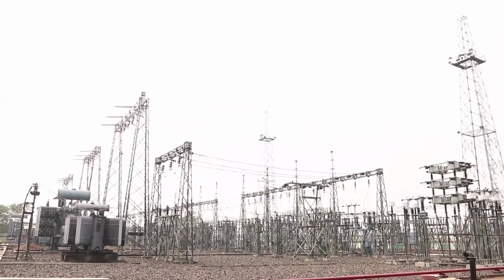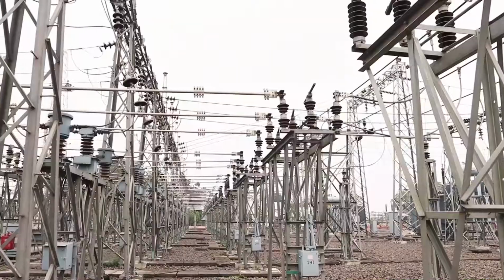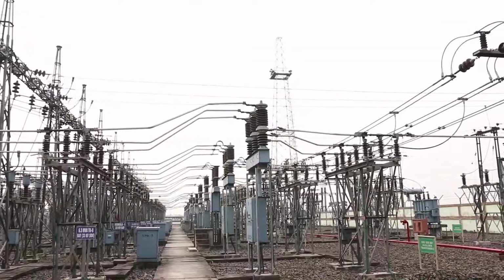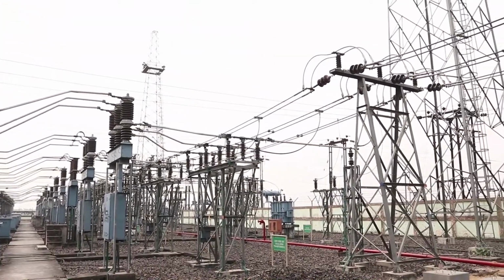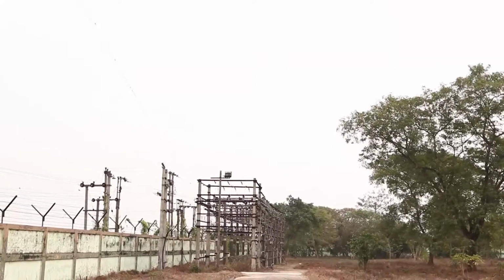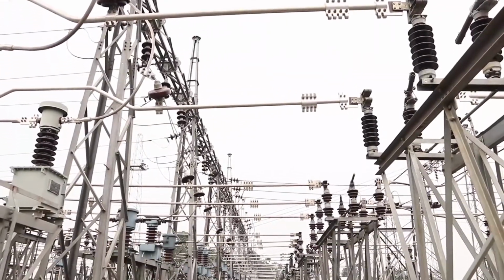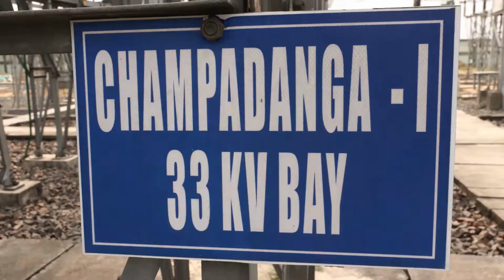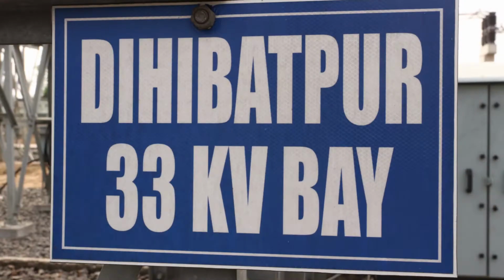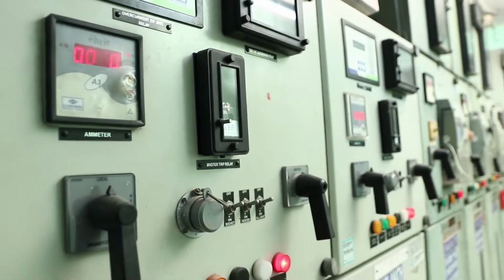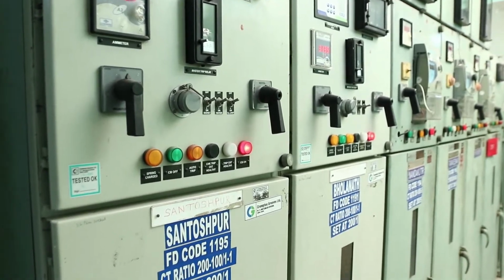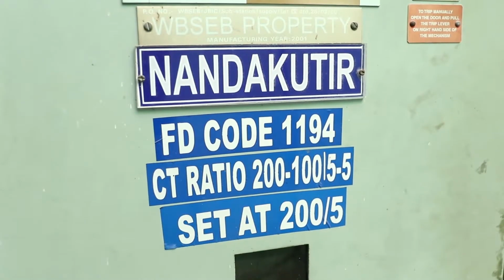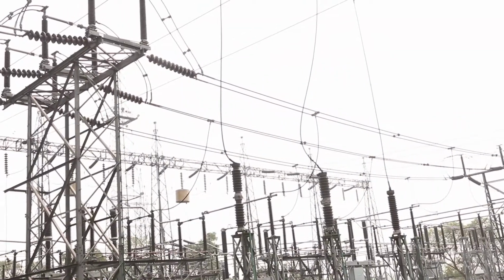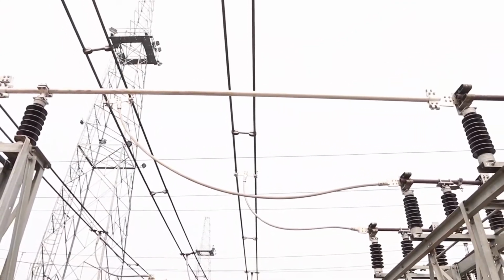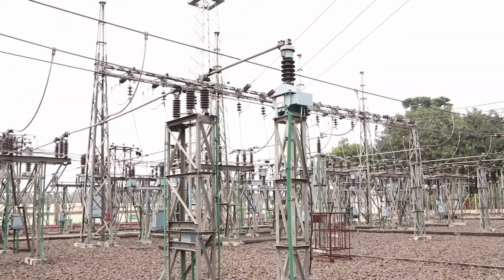Tarakeshwar 132 kV substation delivers power to 33 kV substations, namely Chapadanga, Dihibatpur, Doshkora and Koikala 33 kV substations of WBSETCL. There are 6 numbers of 33 kV feeders, namely Chapadanga 1 and 2, Koikala 1 and 2, Dihibatpur and Doshkora, and 6 numbers of 11 kV feeders, namely Santoshpur, Bholana, Nandakuti, Tarakeshwar, Doshkora and Lokna. This substation has 2 main bus and 1 transfer bus scheme for 132 kV and 33 kV voltage levels.